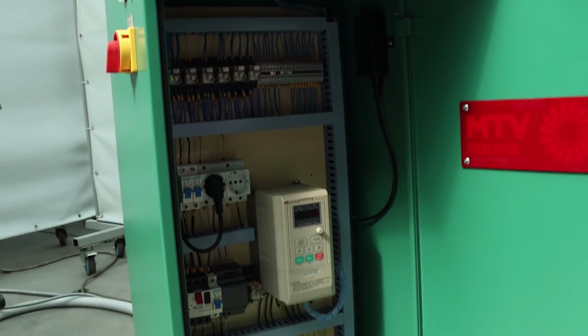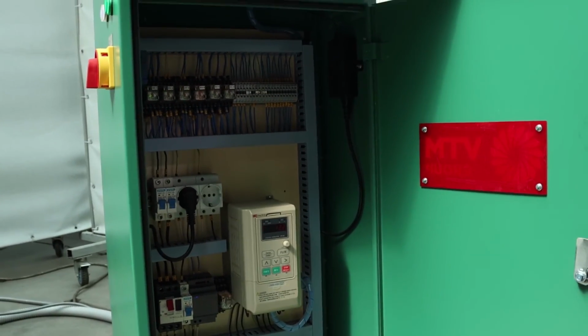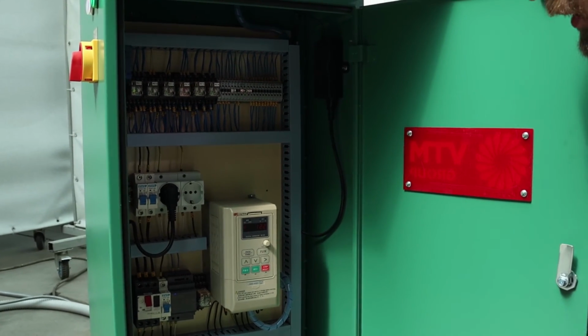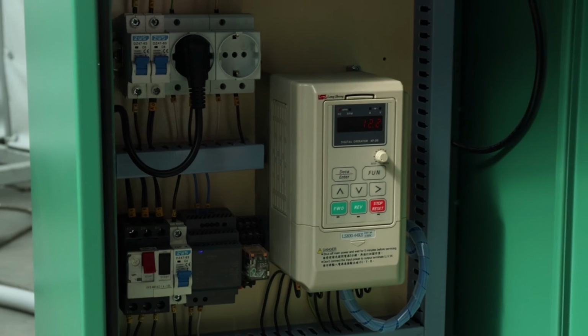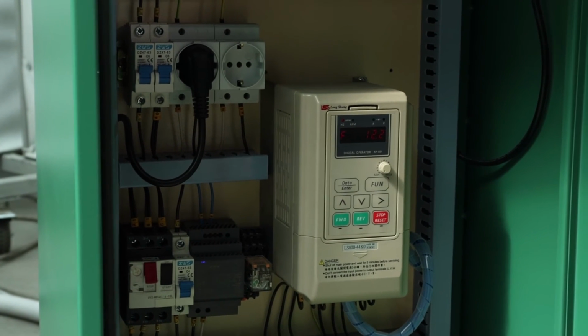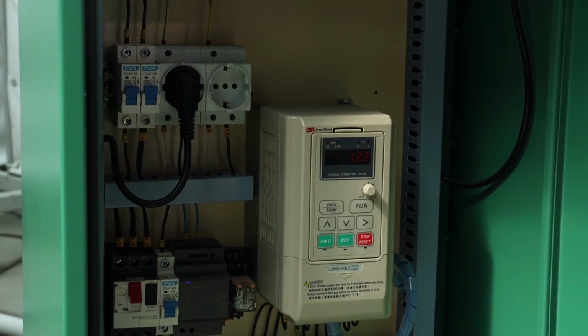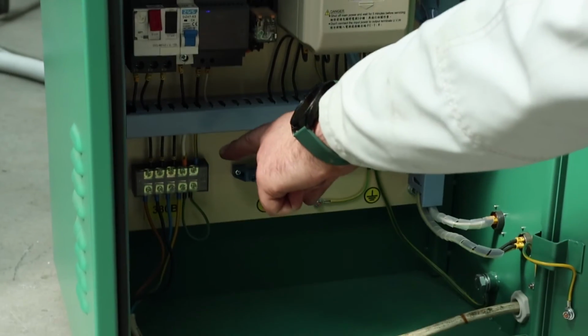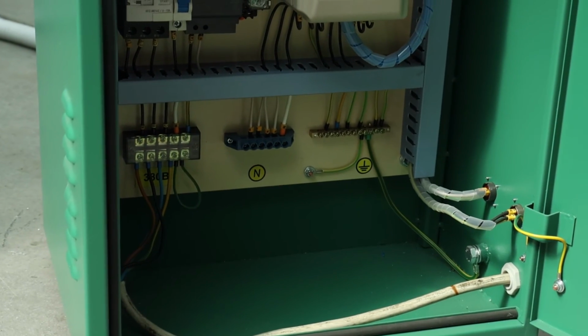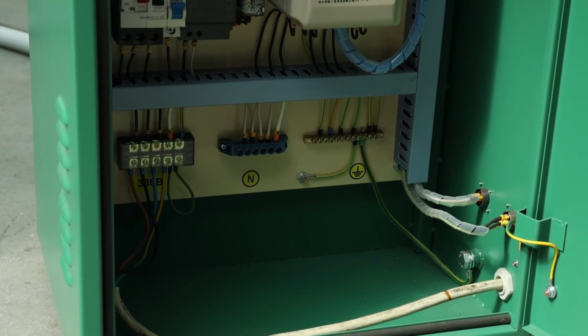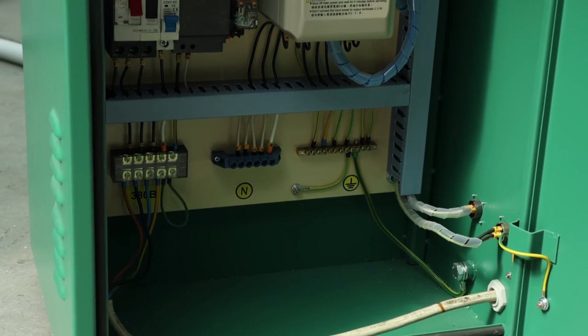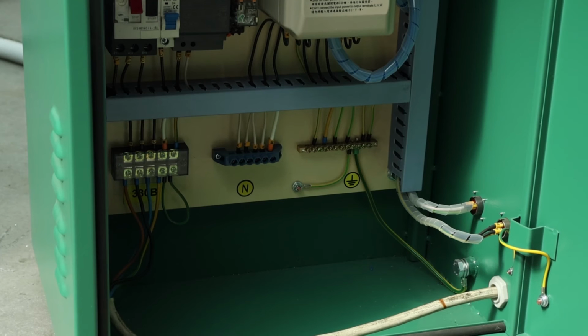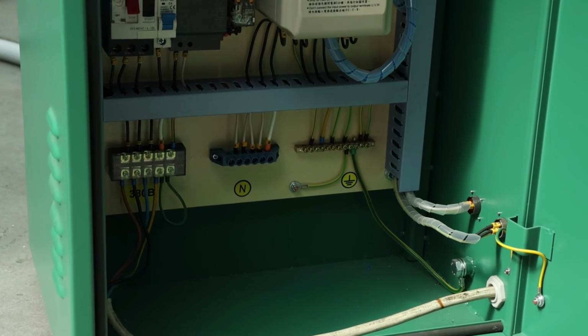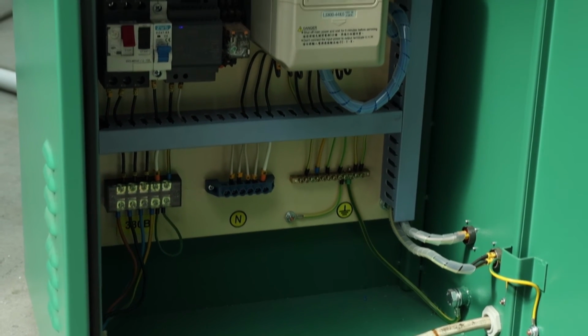At the front there is an electric panel responsible for the drive of the machine. It's got a frequency converter, several power supplies, and a motor protection circuit breaker. The input cable is connected to the terminal box on the bottom left. 5 wires must be used for connection, which means 3 phases, earth and 0.